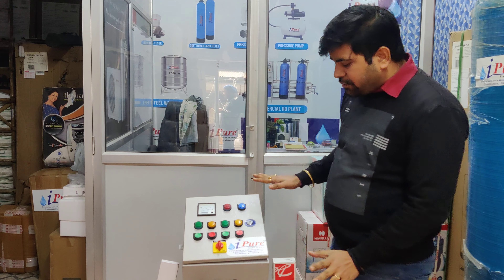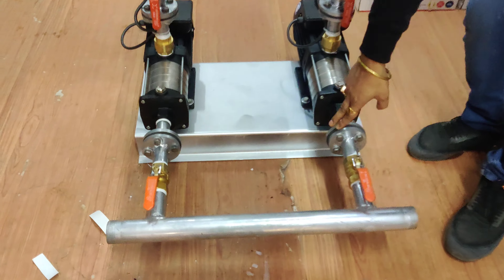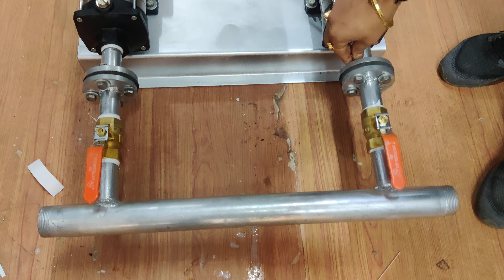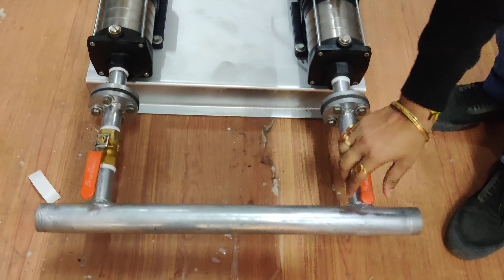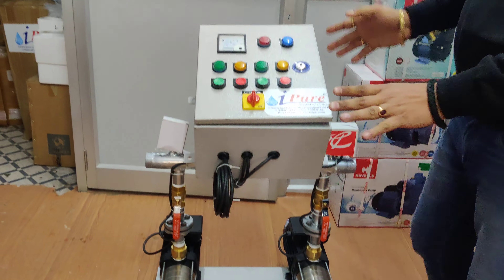This is an overall unit — you can see all the components. We don't use union, we use flanges so we can open the pump in an easy way. If it needs a nut, we will open it. This pump is easy to service — we put ball valves so that it is easier to remove the pump. It will also work well for plumbing.